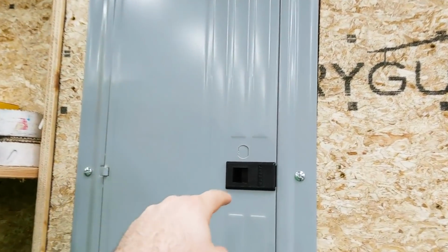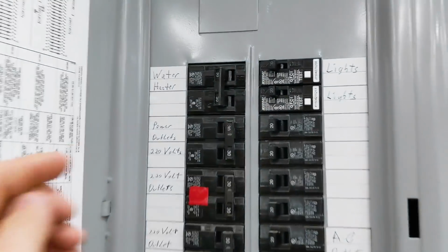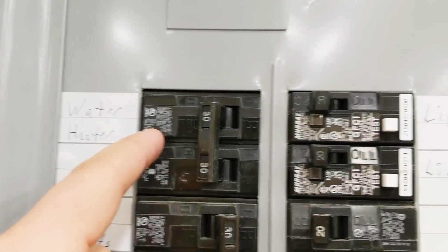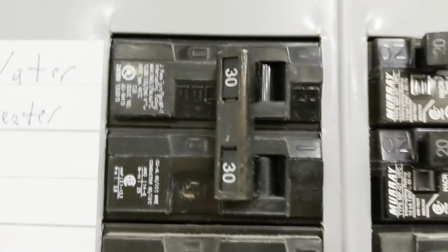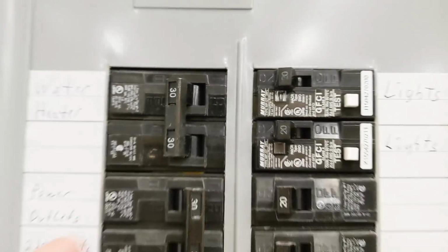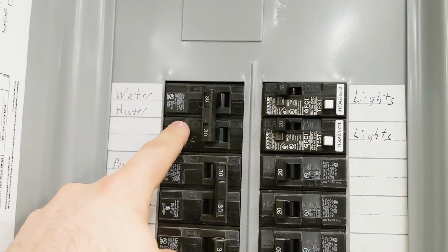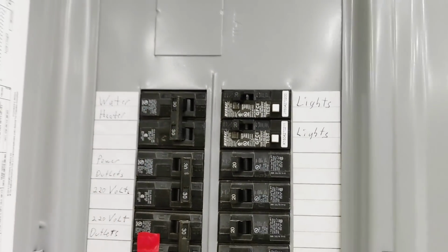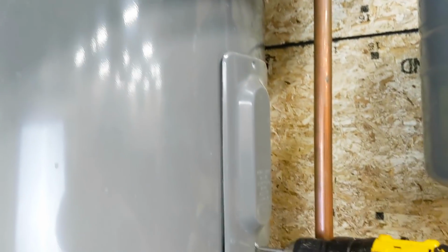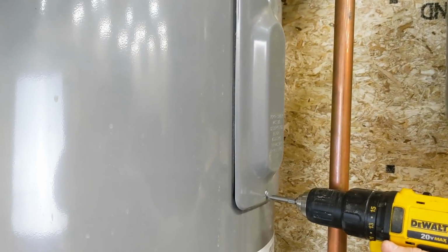So right here is where we're going to turn off power. This top circuit breaker is the water heater, and it's off right now. It's on a 30 amp circuit breaker, which means it's using 10 gauge wire, and that's also what I saw over there. So first we'll take off the top heating element cover.